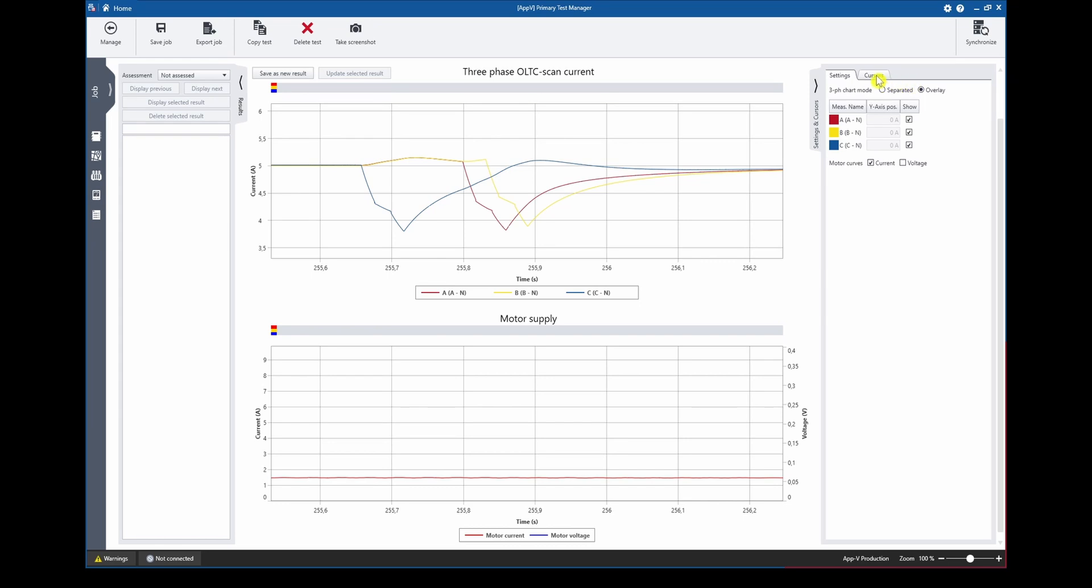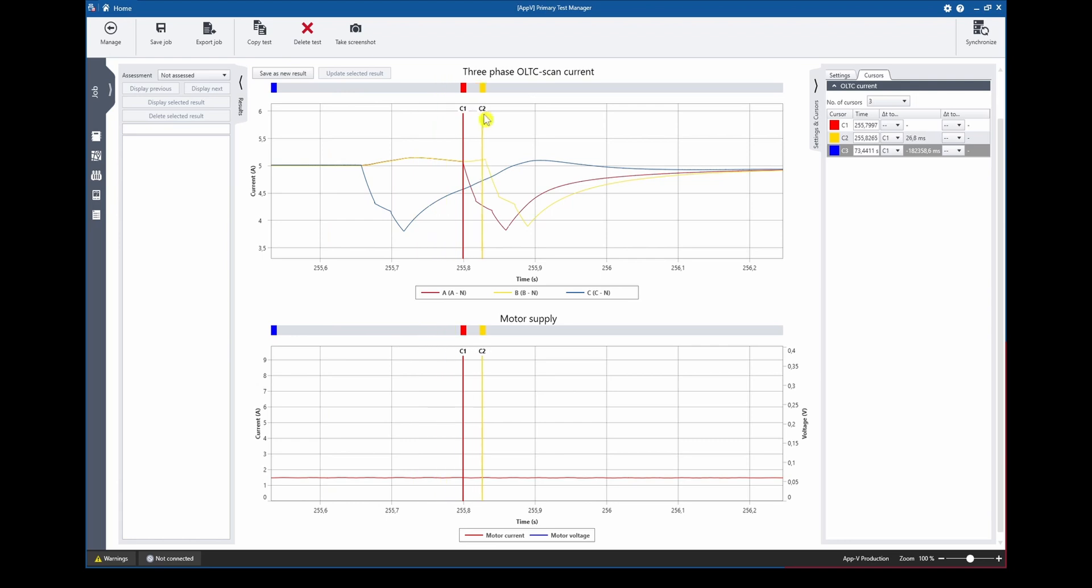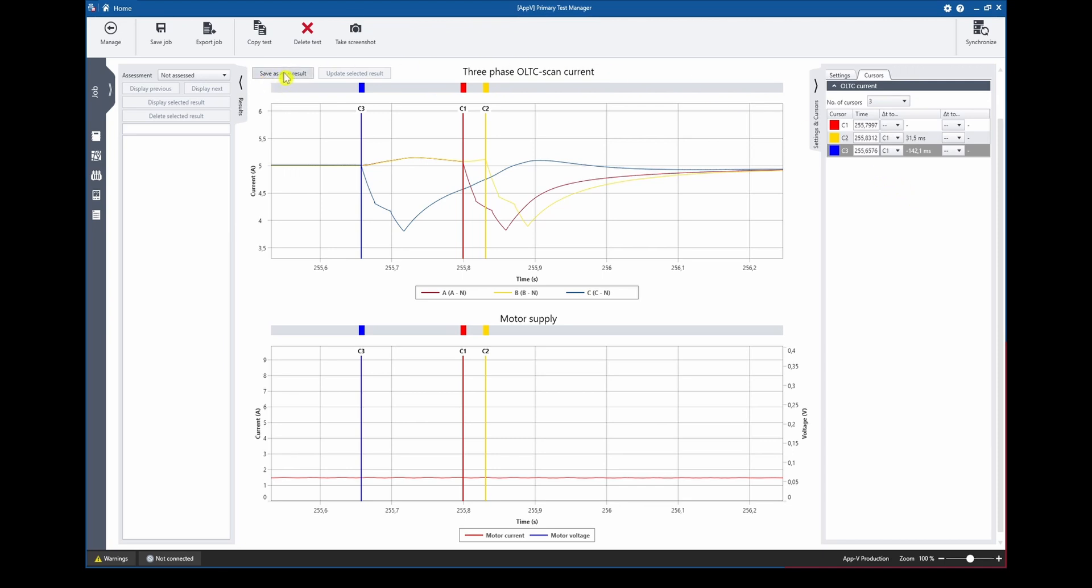We can select up to 12 cursors and place them for example on the beginning of each tap switch operation to measure out the timings. If we do so and we are content with results we can press save as new result to add a new snapshot to our result list.